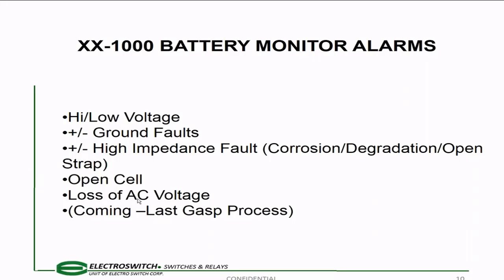Loss of AC voltage is an important aspect. A lot of non-utility locations may have no loss of AC alarm. Like a wastewater facility I walked into: they had lost AC to the chargers, went 3 months, and then they had an outage and had no control of their breakers and system protection devices. That was a real issue, besides the fact that they lost the battery. So they had to get a new AC charger, they had to get a new battery, and they had lost control.